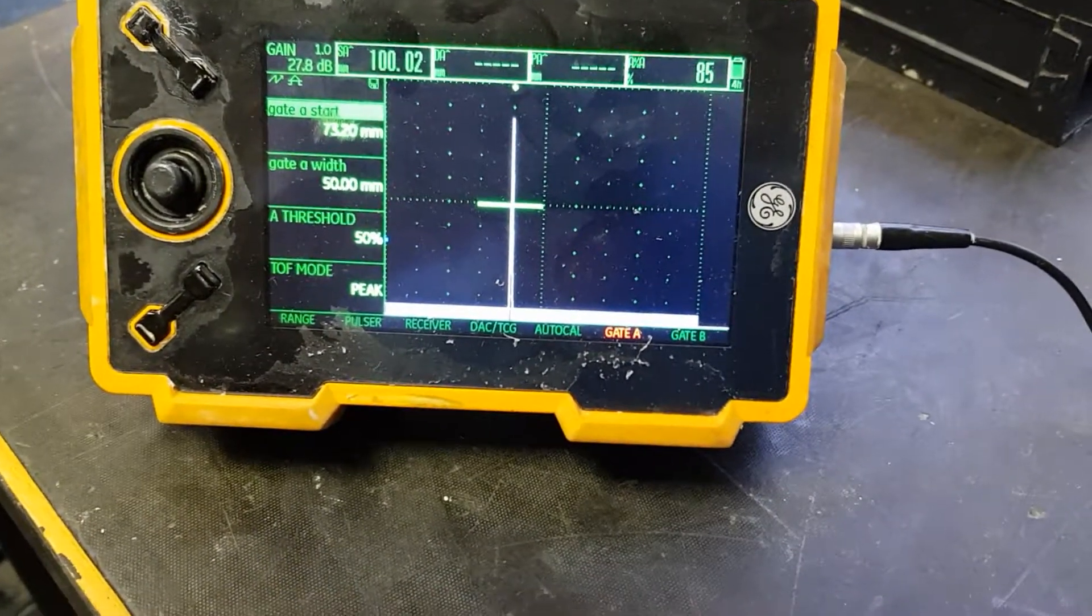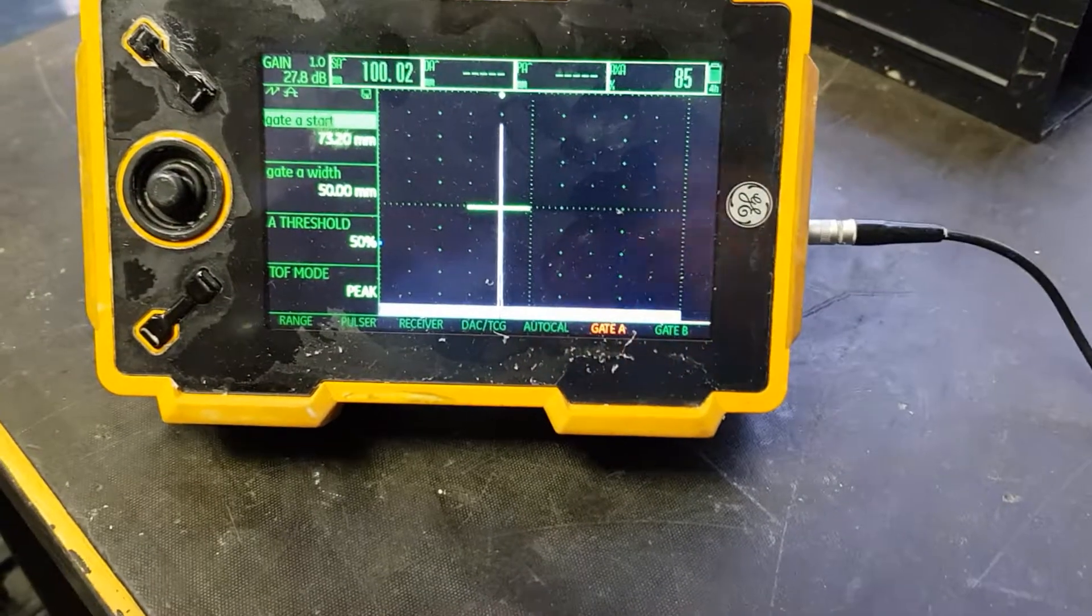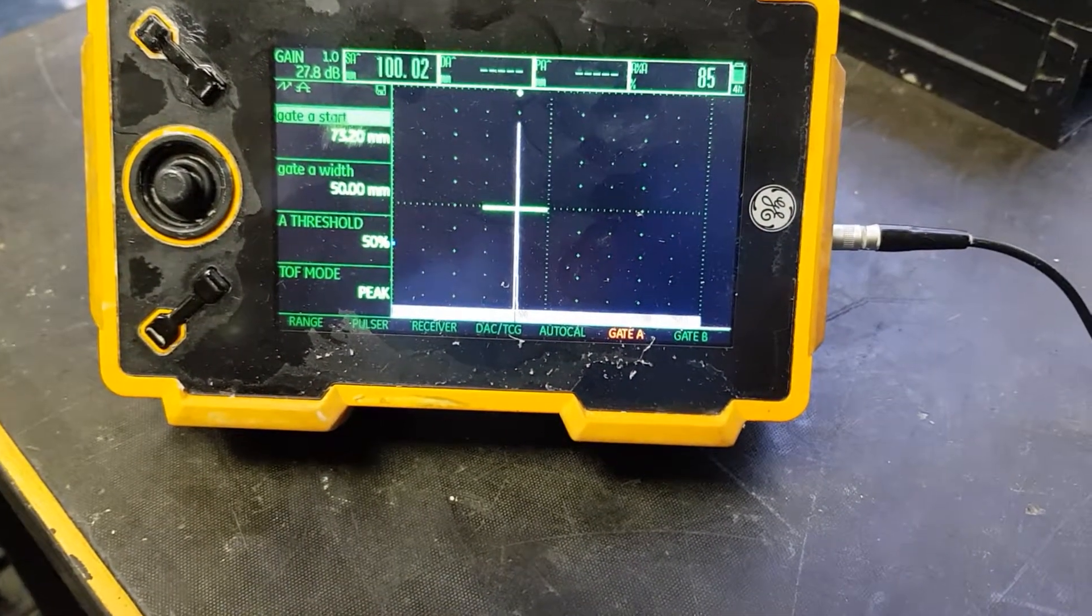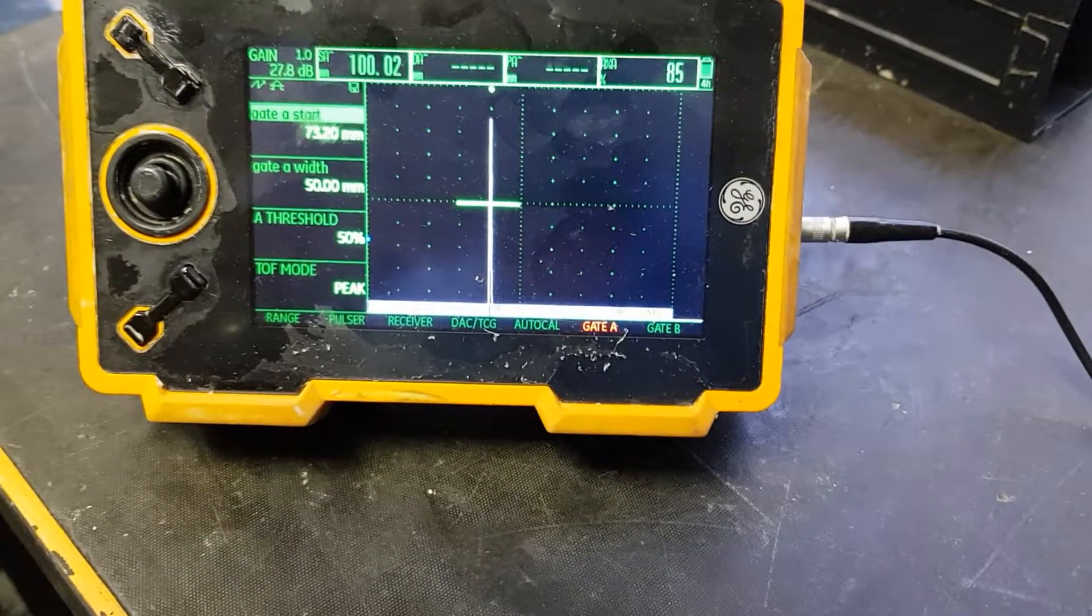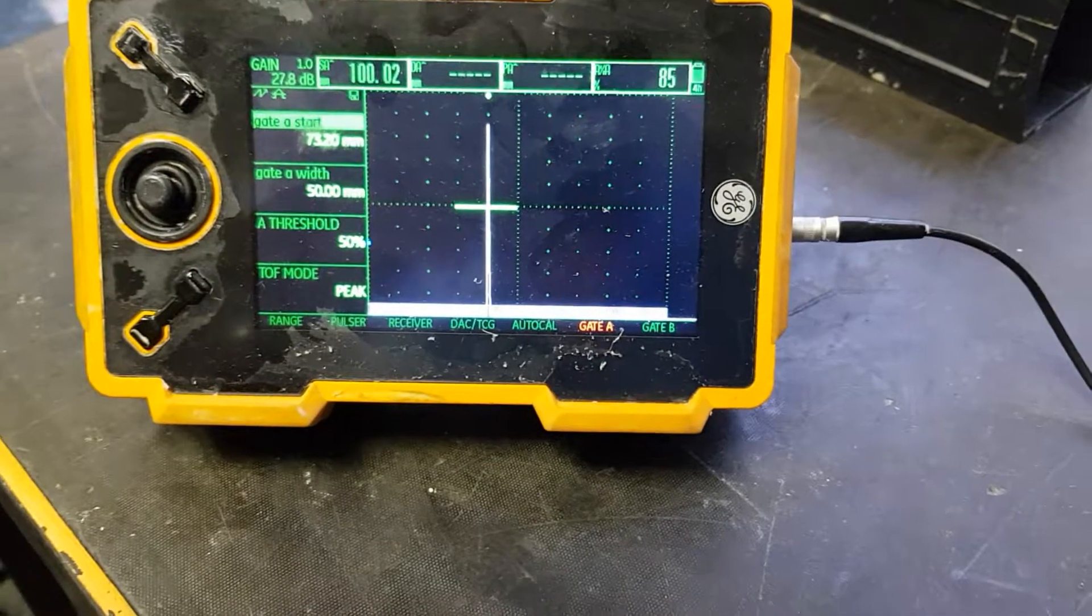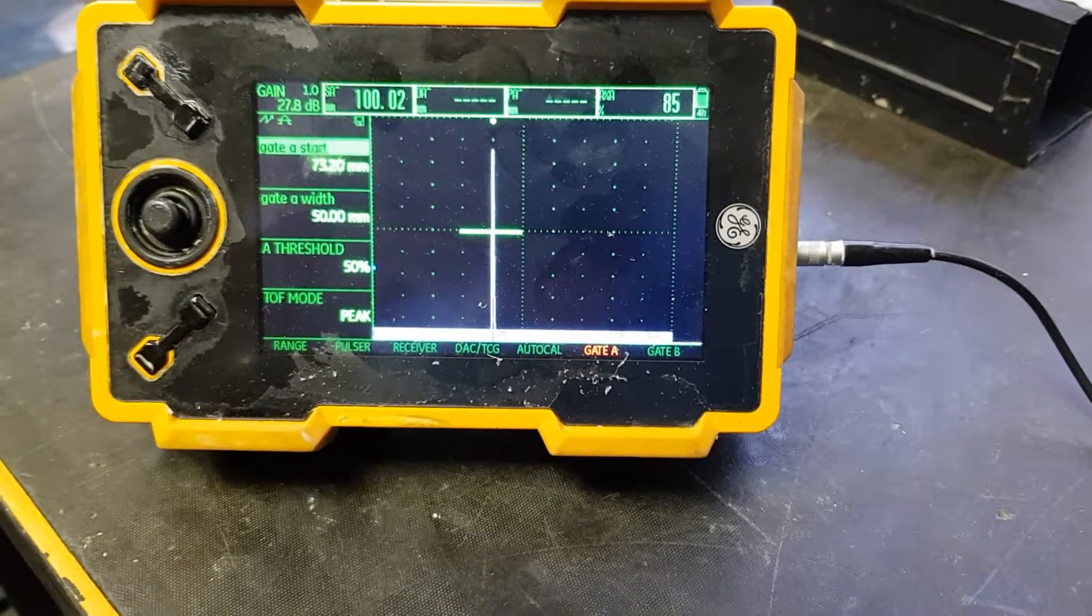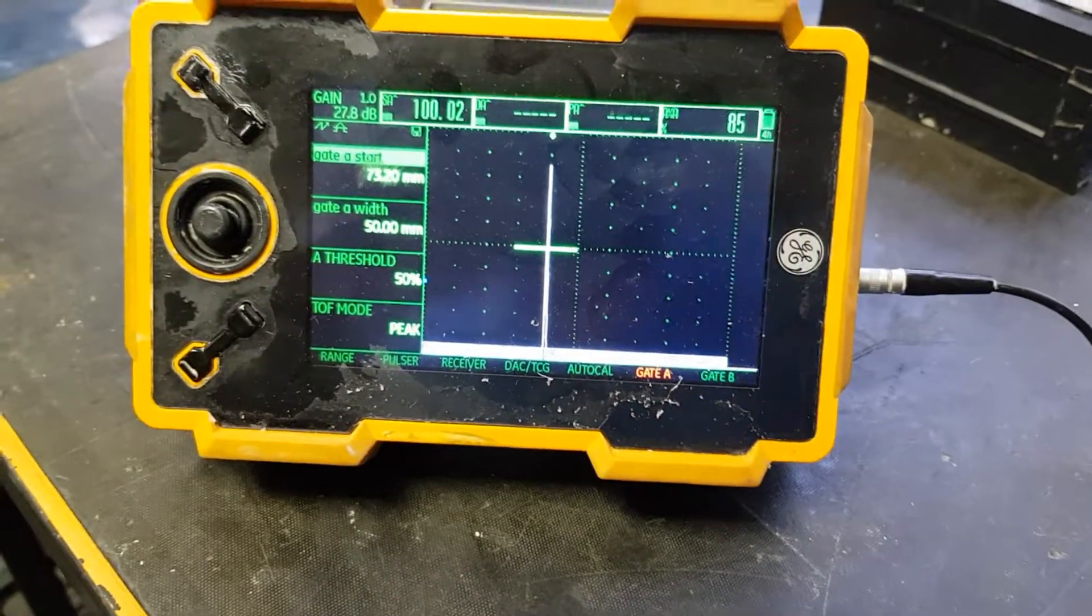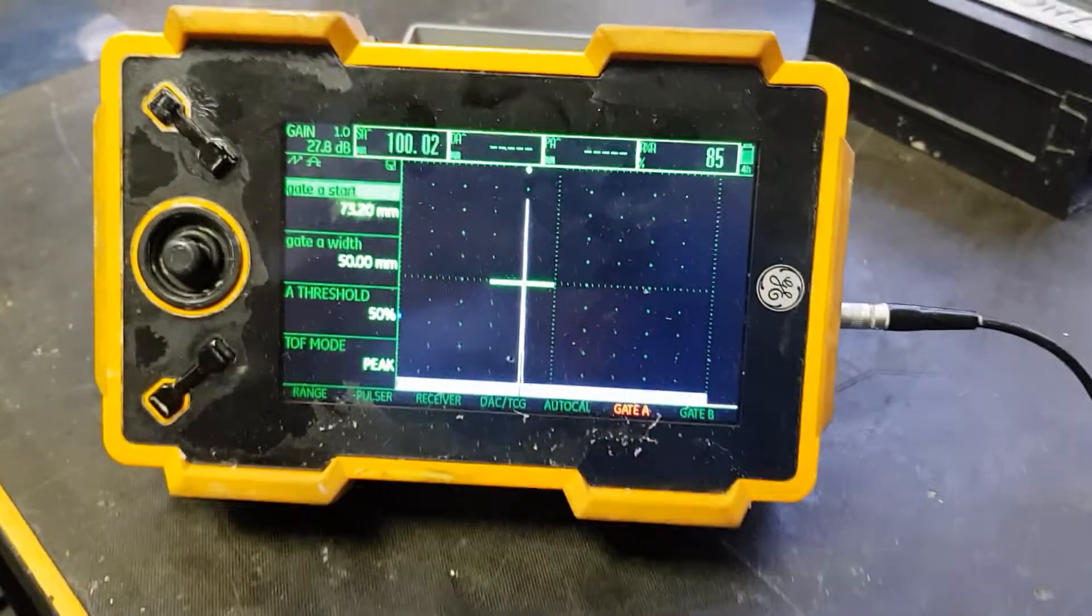If it's a little off, we adjust the probe delay and then the velocity for the second one. Repeat the probe delay adjustment, then velocity, until it's calibrated. Then you can say this is calibrated.